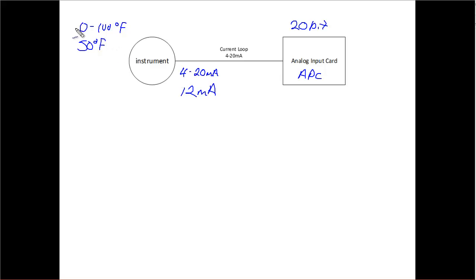Because 4 would be 0 degrees, 20 would be 100. So 12 milliamps is going to be 50. 12 milliamps is going to go into this analog card which is then going to convert it. And I know at 20 bits that I get a resolution. I'm going to be between 0 and 1,048,576.